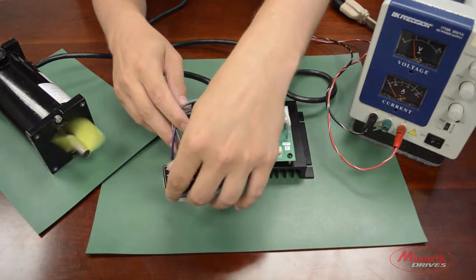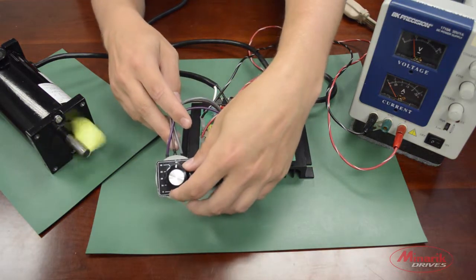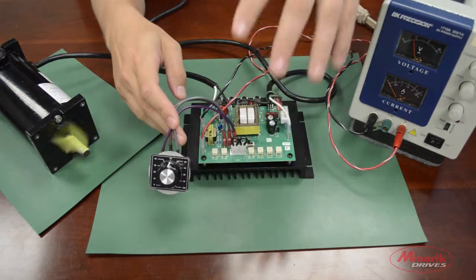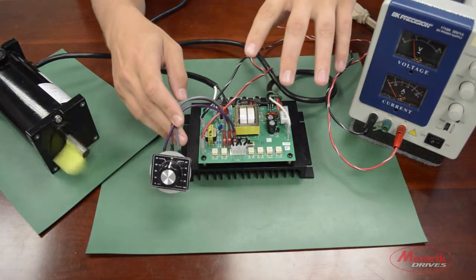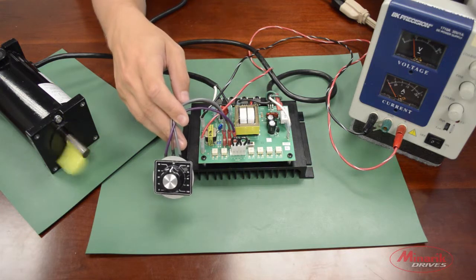And if we were to set the speed potentiometer to 50, the drive will now only see 50% of the input voltage signal which is 3.5 volts.